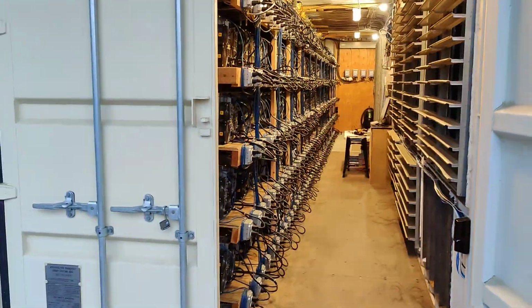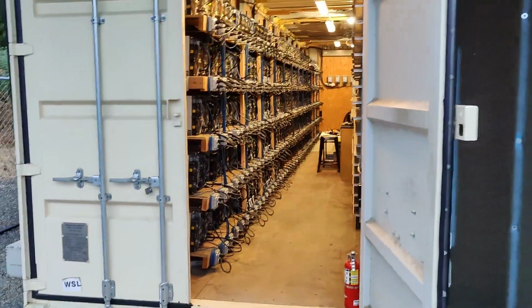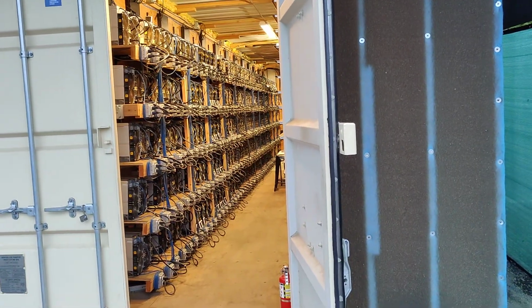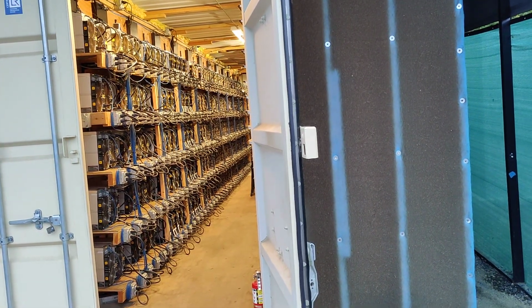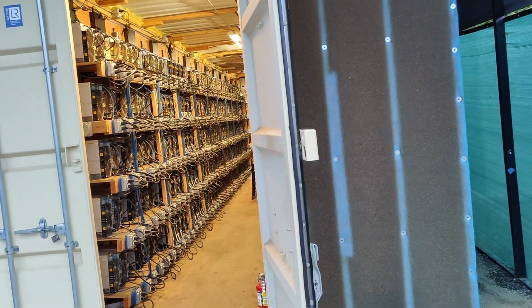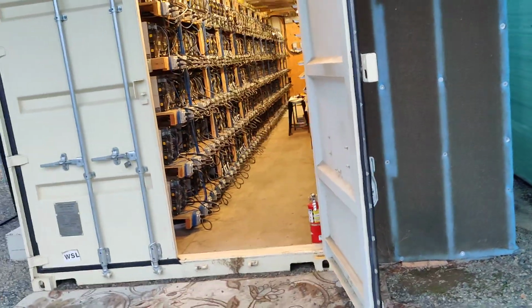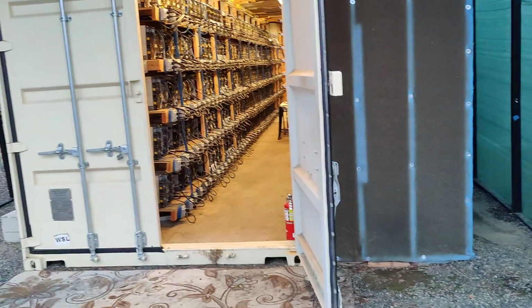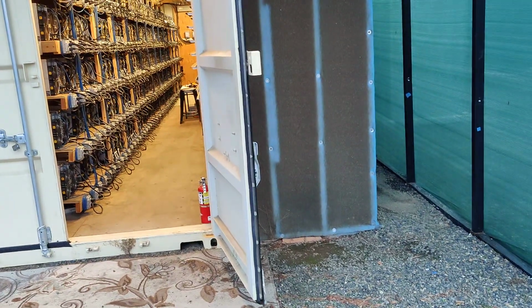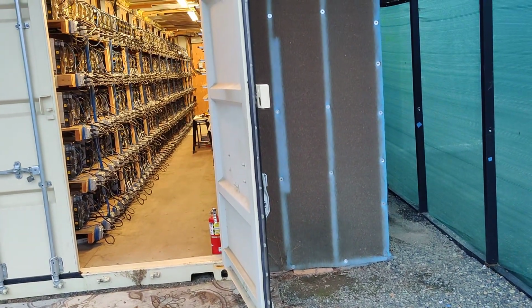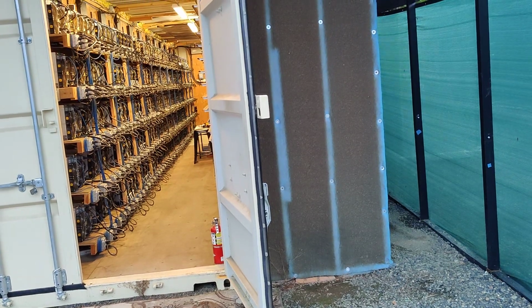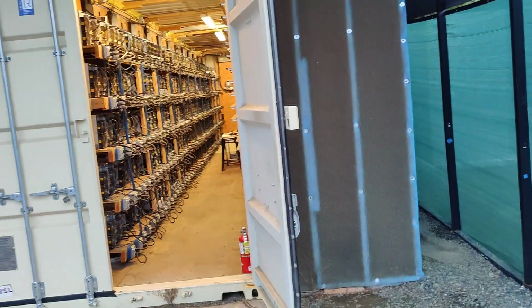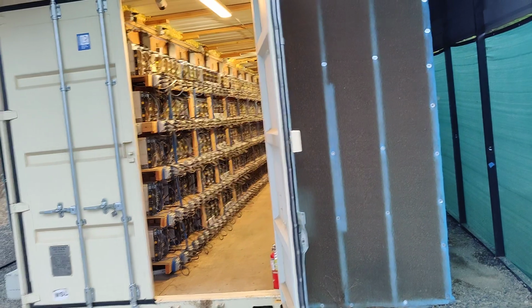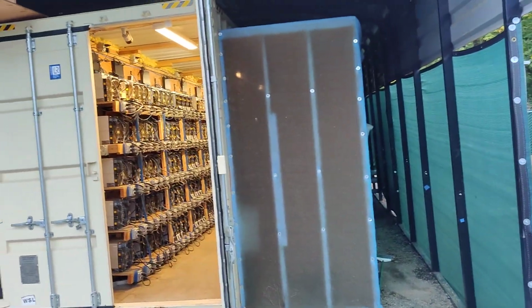So what we're trying to do is we're trying to stop the humidity from reaching 90%, and we're checking two sides of the fan. So if one of the sides is less than 90, let's say one of the sides is 80 and the other side is 93, then that's what we want. That's perfectly fine because that 93 and 80 will mix together and create something like 85. And 85 is less than 90, so that's the value we're looking for.